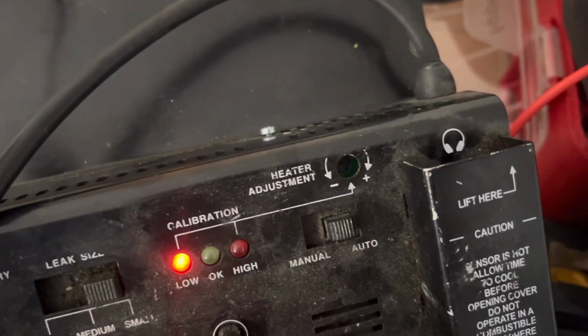Just a little uptick, and that's why I ordered a new sensor. Now I could make this sensitive enough by, there you go. You see that heater adjustment right there? I can turn up the heater, and this is an old secret. It's not too much of an old secret, but where did I put my screwdriver? Well, I lost it in the mess. But I can turn up the heat on this sensor and make it more sensitive.